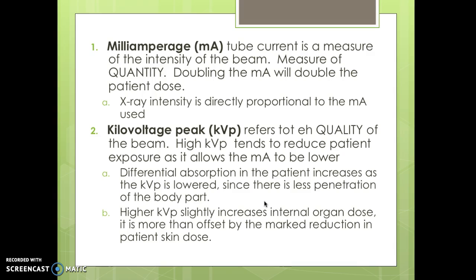When we talk about milliamperage (mA), that's the tube current, measured as the intensity of the beam. It's measured as quantity — doubling the mA doubles the patient exposure or dose. So the x-ray intensity is directly proportional to the mA used.